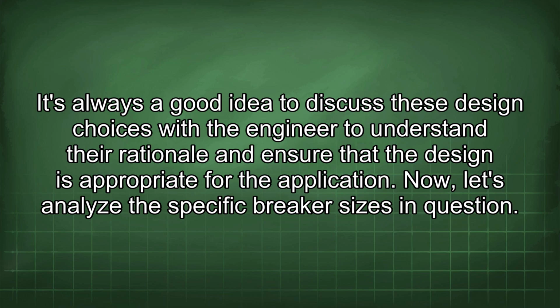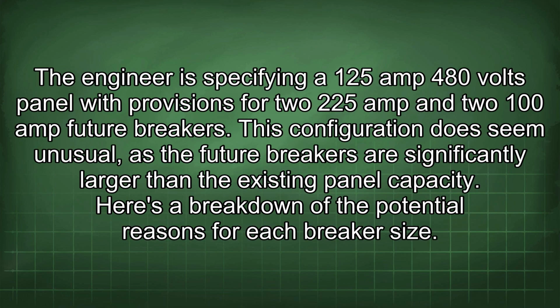Now let's analyze the specific breaker sizes in question. The engineer is specifying a 125 amp 480 volts panel with provisions for two 225 amp and two 100 amp future breakers. This configuration does seem unusual, as the future breakers are significantly larger than the existing panel capacity. Here's a breakdown of the potential reasons for each breaker size.